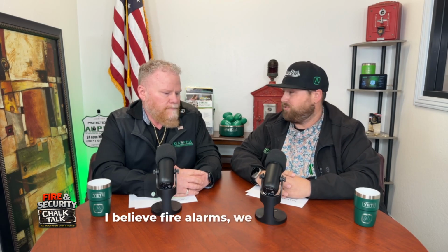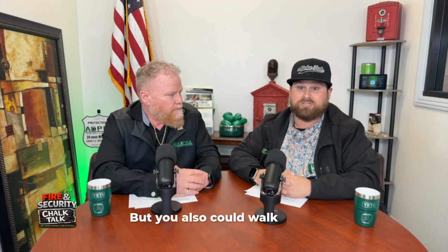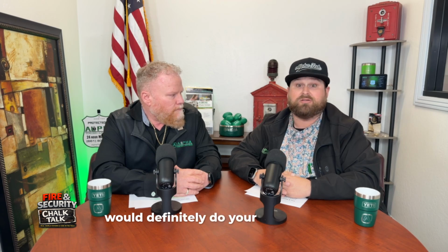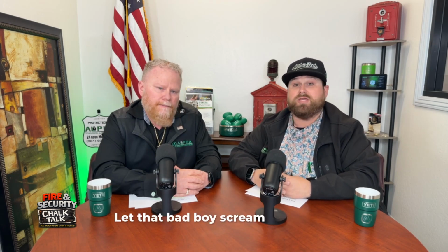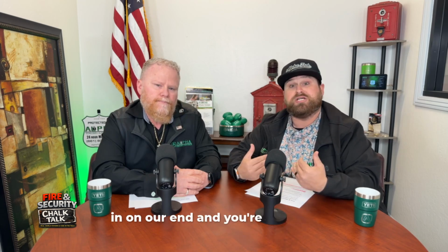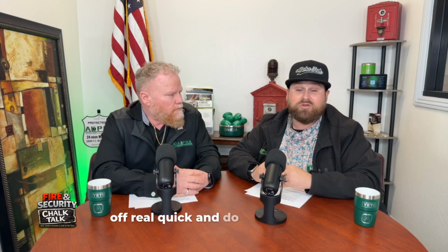I believe fire alarms, we can do walk tests now. You just have to call us so we can put your system on test for you, but you can also walk it. But for security, I would definitely do your house once a month. Call us in, we put your system on test and set that bad boy off. Let it scream for over 10 minutes so you can see everything, so we make sure we're getting everything coming in on our end and you're good to go. It's not that hard to set your system off real quick and do it every month.